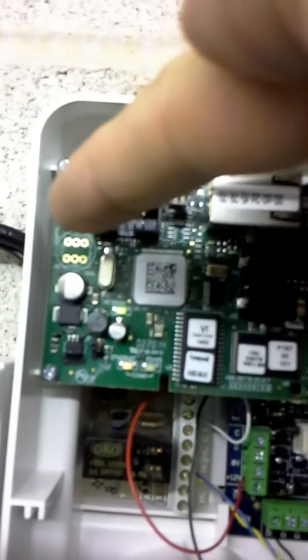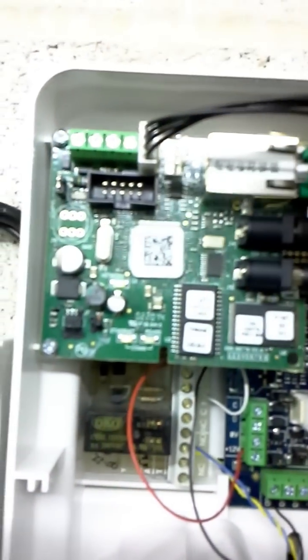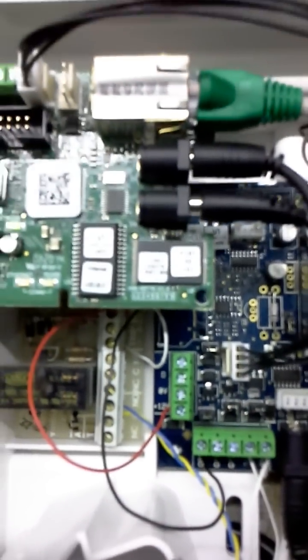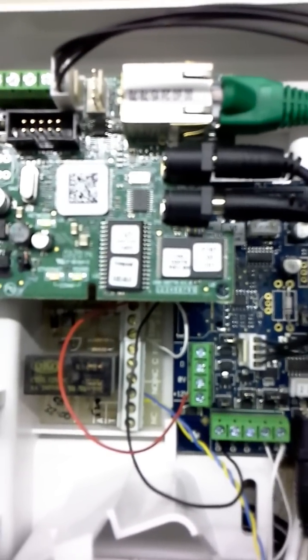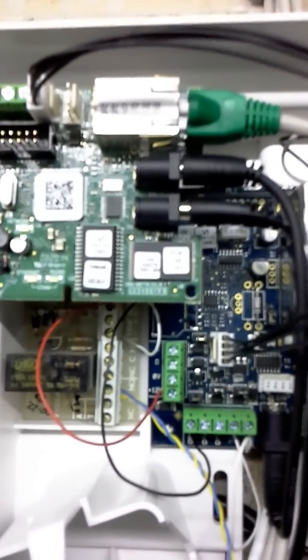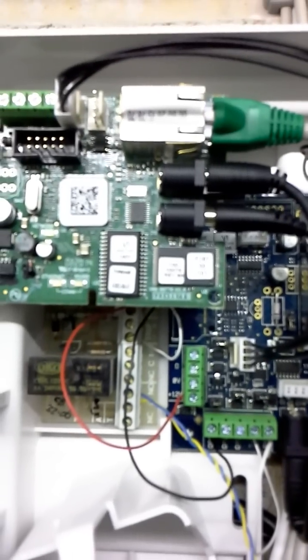This cable up here is a jumper cable that connects to this part of the board here, making sure that this P3 panel link is on here. Once you've done this, you can go to option 72, go to network automatic detect, and you should detect an extra comms module.